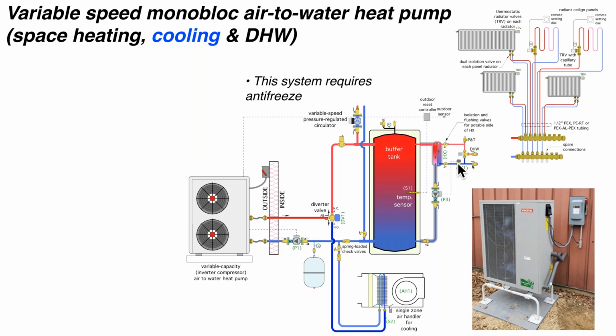There's a flow switch here. This determines whenever you draw domestic hot water and the flow gets above roughly 0.7 of a gallon per minute. This switch would sense that. It's going to turn on this circulator. We're drawing warm water from the top of the buffer tank down through the primary side of the heat exchanger and putting it right back in. And our cold domestic water is going up in counterflow and getting heat.